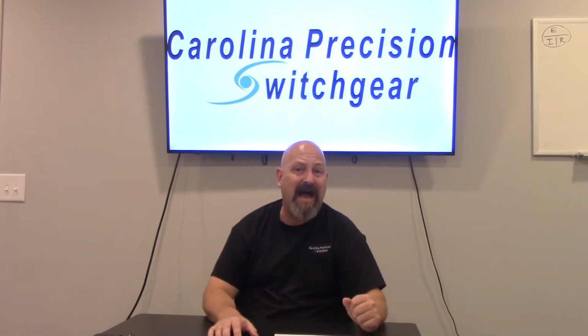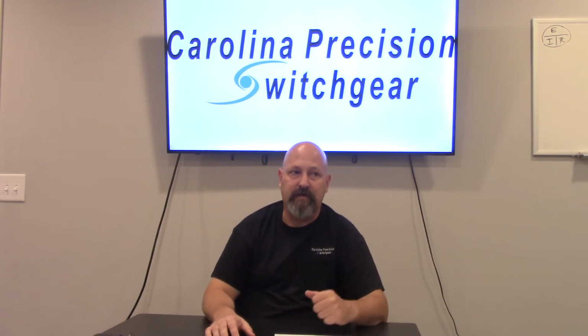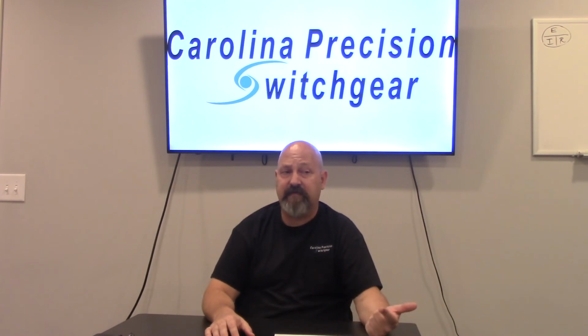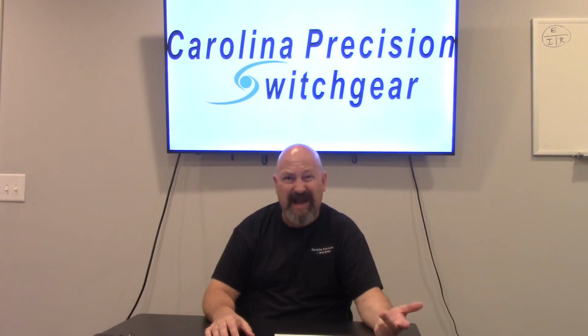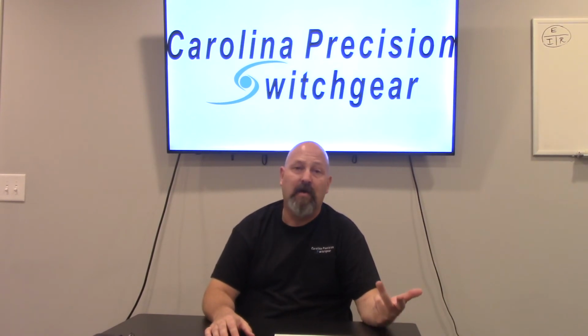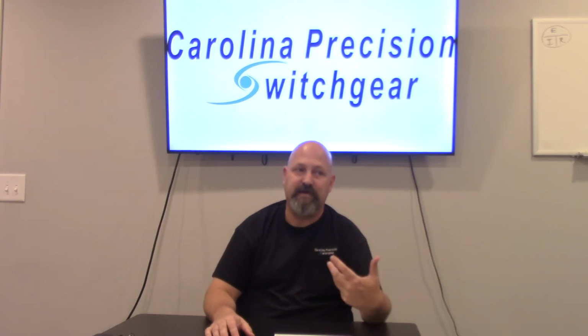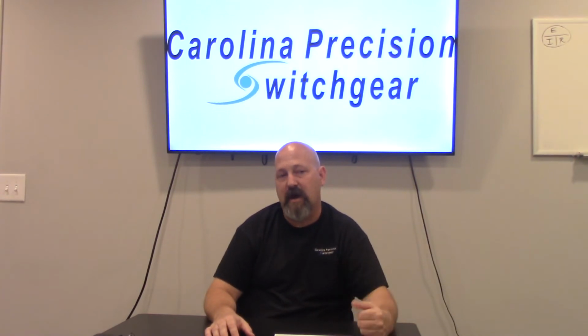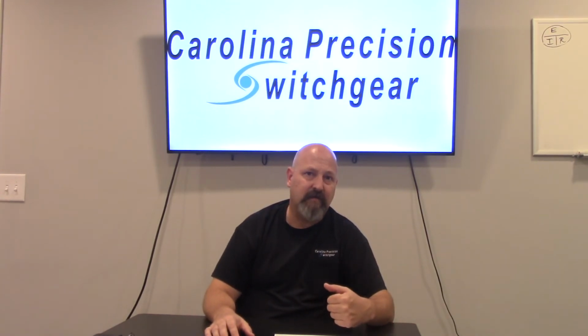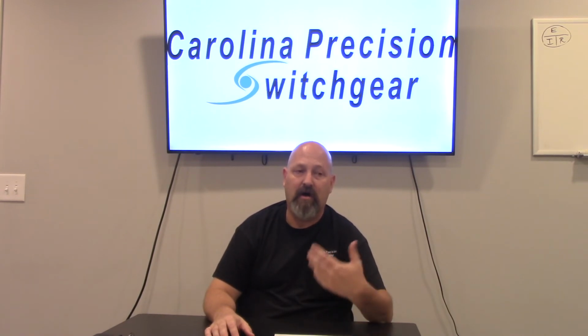There are additional questions that need to be asked when you have a trip. What was going on at the plant at the time? Were they energizing loads? Did a particular piece of equipment fail, which caused the trip? Was there a lightning storm? Was there power problems from the utility? These can all affect your system, causing abnormal operation of devices within your plant, which can then cause current draw, which can trip the circuit breaker. So most important is to figure out why it happened, isolate the breaker, and then you can reclose the breaker and see if it holds.